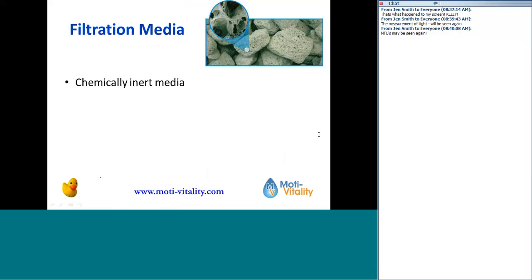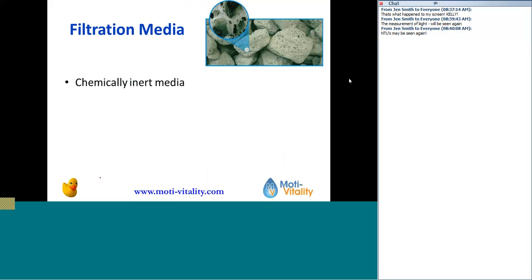Okay, I have a question here. Let's see. What would cause a neutralizer tank to become channeled? It could be that it's not backwashing often enough, or not having enough backwashing pressure. That's kind of what happens with mud balls, it forms channeling.